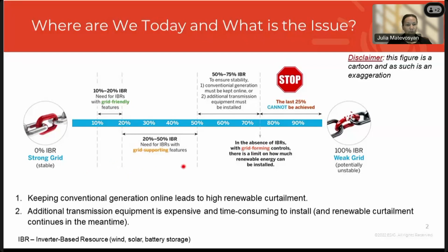Then as we move forward to 20-50% of IBRs maybe, we needed more functionality from inverter-based resources and asked for grid supporting functions such as frequency control and voltage control and dynamic voltage response, dynamic reactive response, sorry. And then as we now progress towards 50-75% of inverter-based resources in some areas, we're already starting to get into some kind of constraints associated with weak grid issues, maybe in some more meshed areas that have a lot of inverter-based resources. These are also related to frequency and inertia issues.